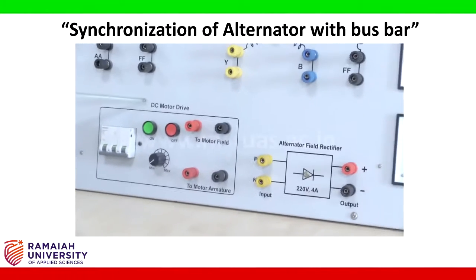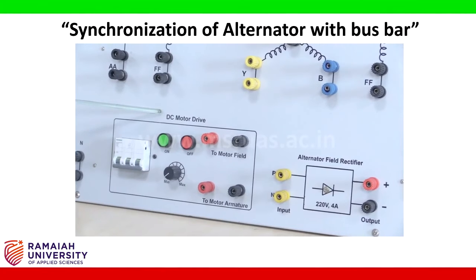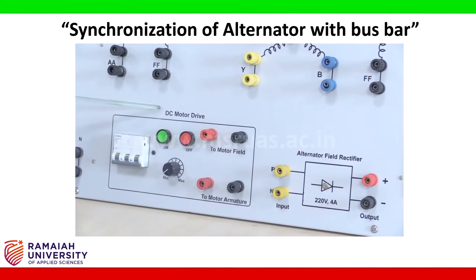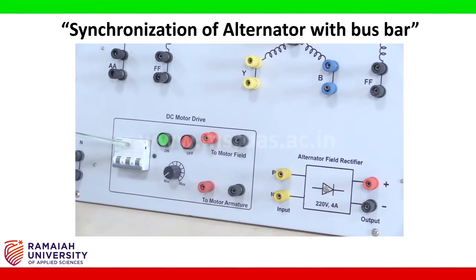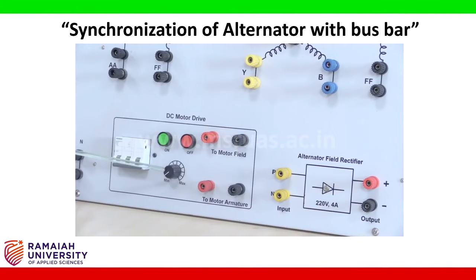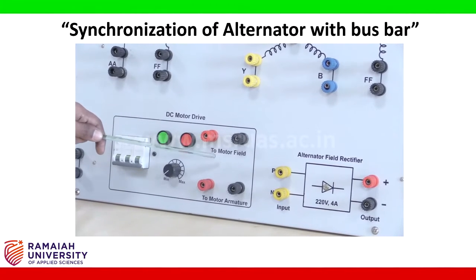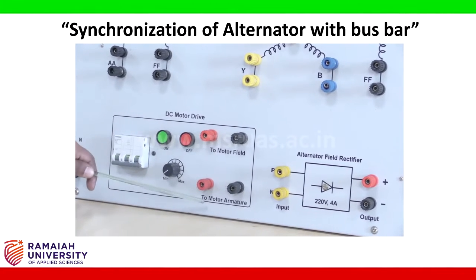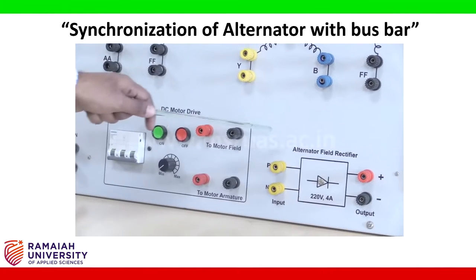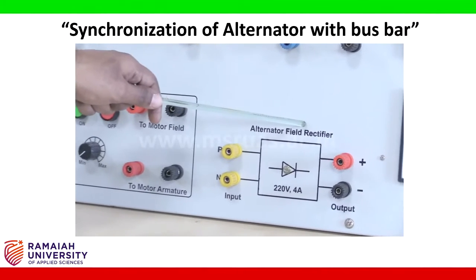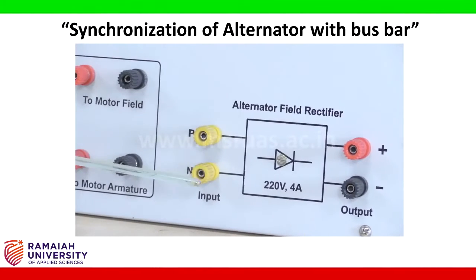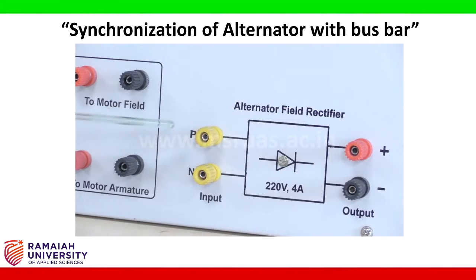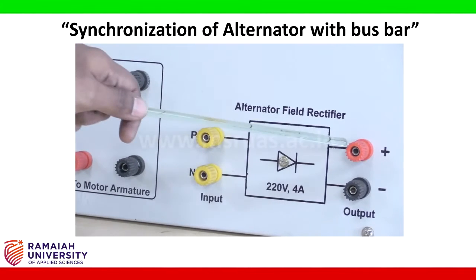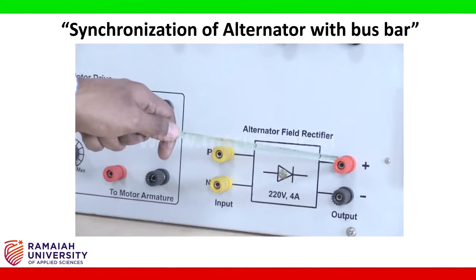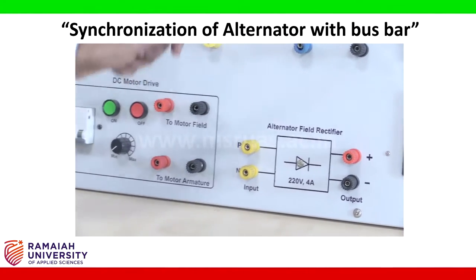Coming to here, this is the DC motor drive. This supplies the power to our DC motor. Here we are having one TPST switch, on off push button, speed control knob and the terminals to connect the motor field, terminals to connect the armature. Here we are having the alternator field rectifier. Alternator requires DC supply for its field, so we are taking single phase AC supply as the input to the rectifier and rectifying that, we are supplying from output of the rectifier to the alternator field.